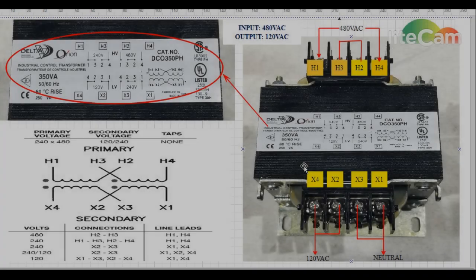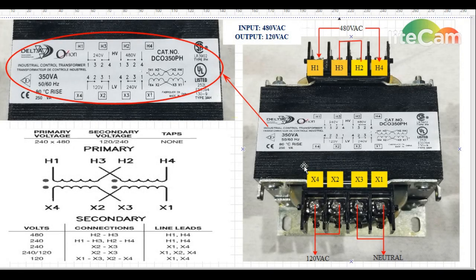Now let's suppose this transformer was supposed to be wired for 240 volts. For that we will be jumping H1 and H3 together. You can see on this diagram 1 and 3 together, and the other set will be H2 and H4 jumpered together, and we will be feeding our main voltage to terminal number 1 and 4. The only difference will be this: instead of feeding a 480 we will be feeding a 240, and the jumpering connections will be interchanged.